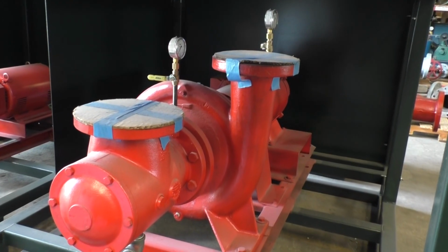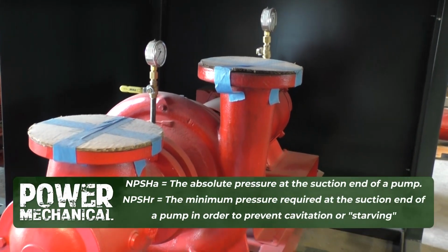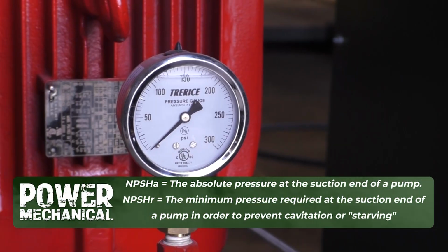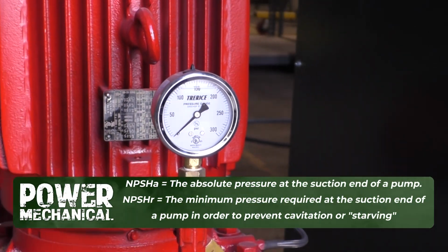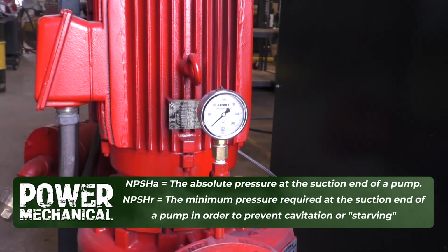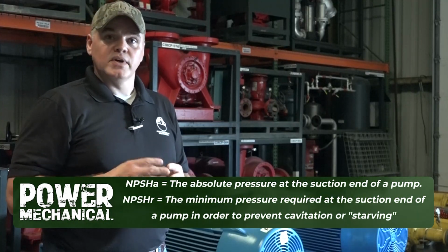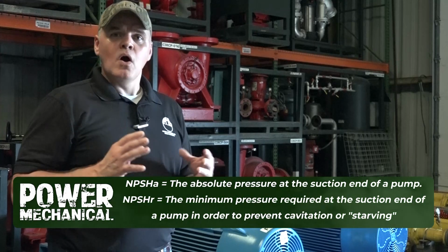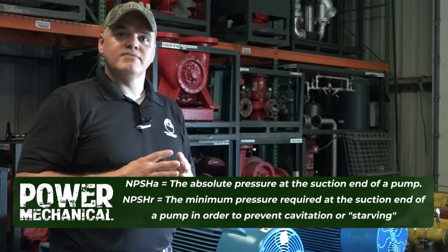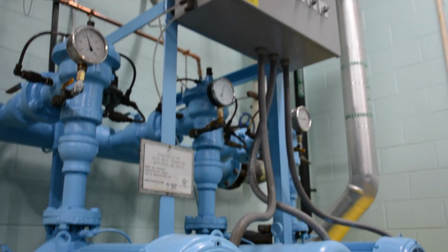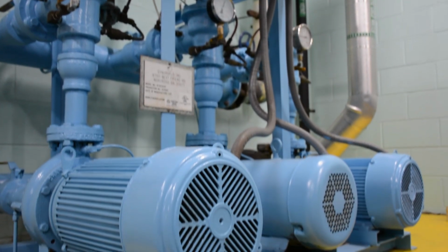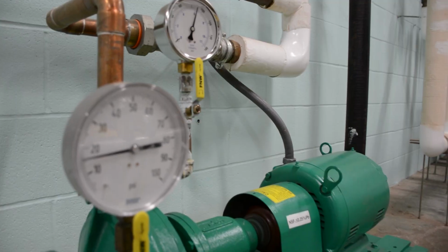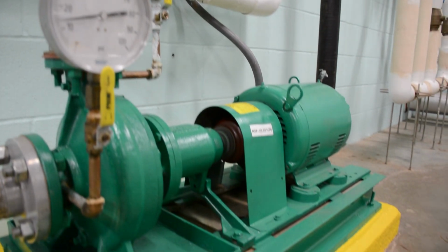Now our NPSHR, or required, is defined from our pump curve and is in short the amount of suction head that the pump requires in order to operate efficiently based on the curve's projections. All that said, if a pump is showing signs of cavitation or vibration, these two values should be compared to ensure that the actual pressure is sufficient for the pump requirement for best performance. This is where our manufacturer's data for our pump, along with properly installed gauges, are critical.